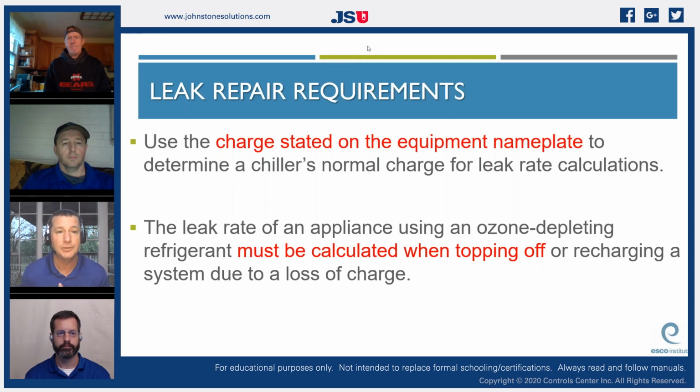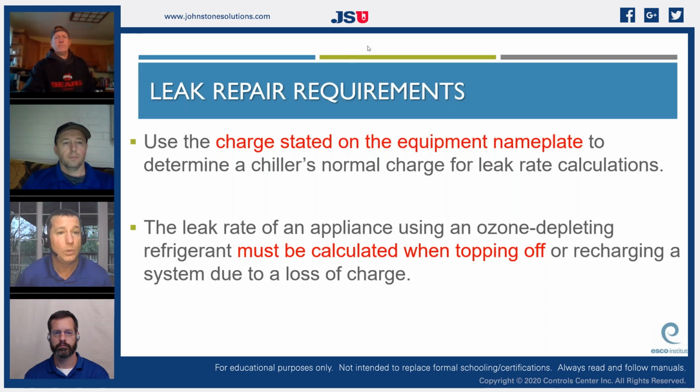So if I'm a service technician, even if I have never been up to this piece of equipment before, we're a new contractor to this piece of equipment, and we're here to take a look at this thing, and I find that my 100 pound system is being used for industrial processing, and I just put 31 pounds of refrigerant in this 100 pound system, I have now hit my leak rate threshold. I've had 30%. So I have to calculate what that total system is. And it might take a little bit of work.